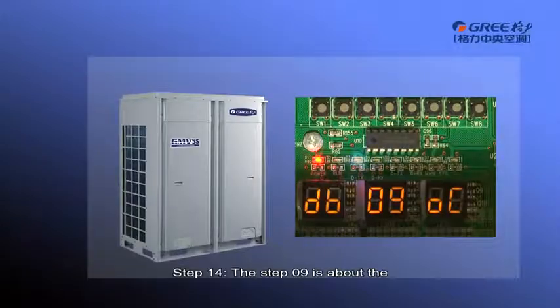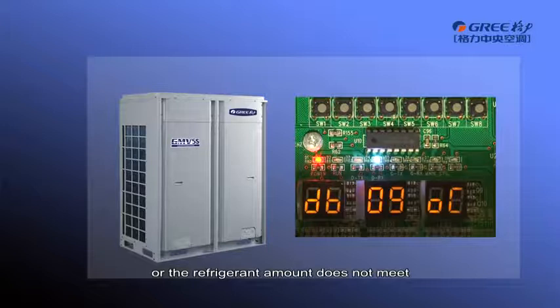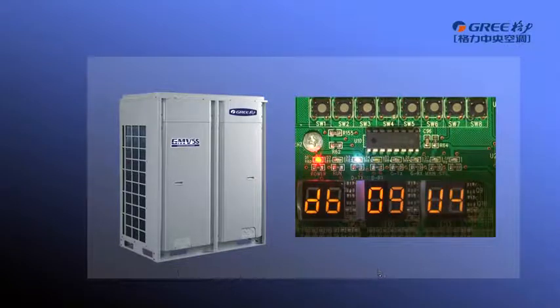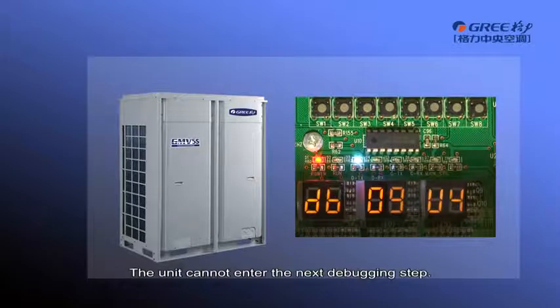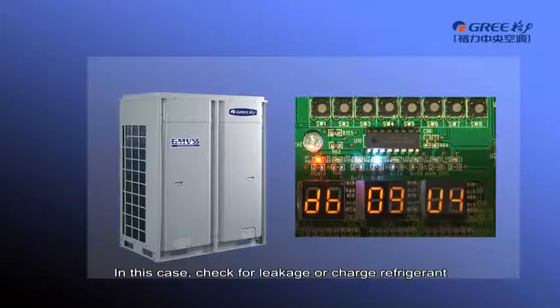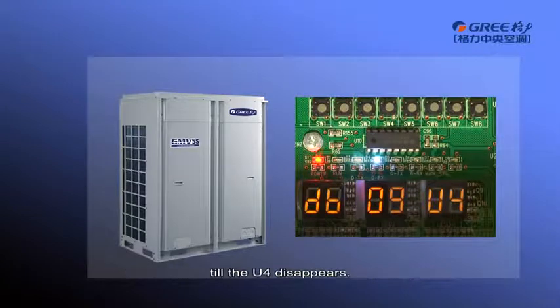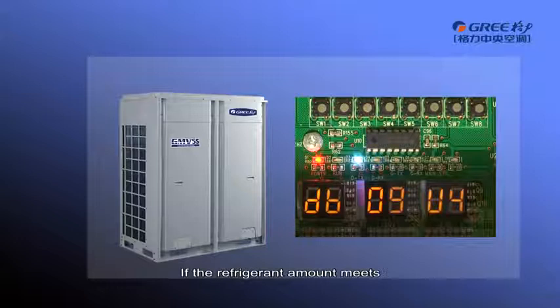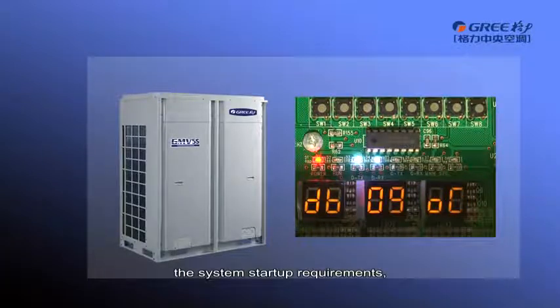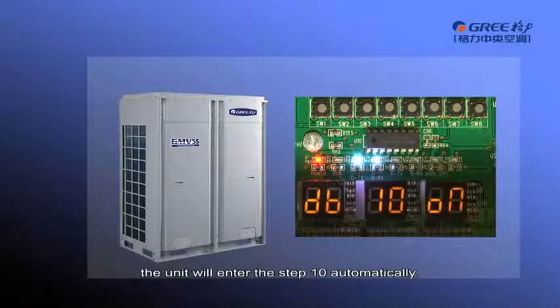Step 14. The Step 9 is about the pre-startup refrigerant confirmation. If no refrigerant in the system or the refrigerant amount does not meet the system startup requirement, error code U4 will be displayed. The unit cannot enter the next debugging step. In this case, check for leakage or charged refrigerant till the U4 disappears. If the refrigerant amount meets the system startup requirements, the unit will enter the Step 10 automatically.